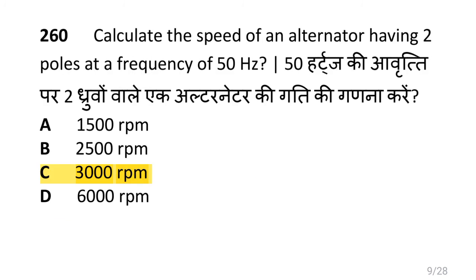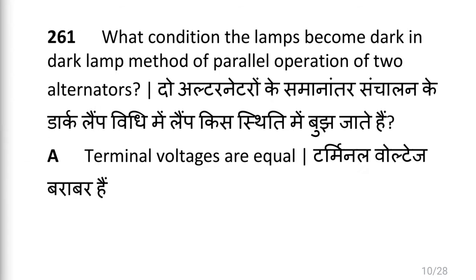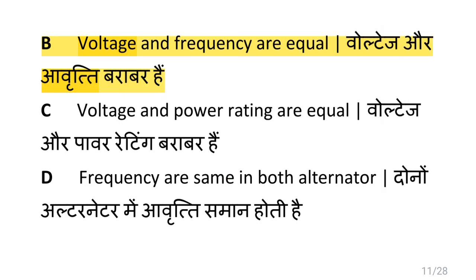Calculate the speed of an alternator having 2 poles at a frequency of 50Hz, i.e. 3000 RPM. What condition causes the lamps to become dark in the dark lamp method of parallel operation of two alternators, i.e. voltage and frequency are equal?